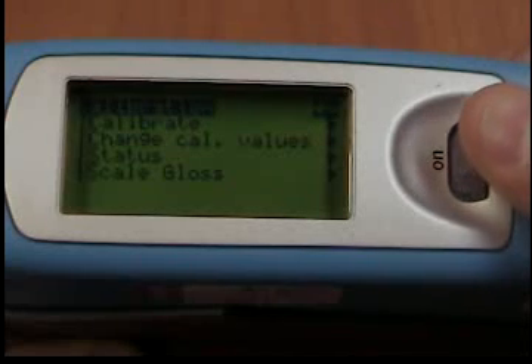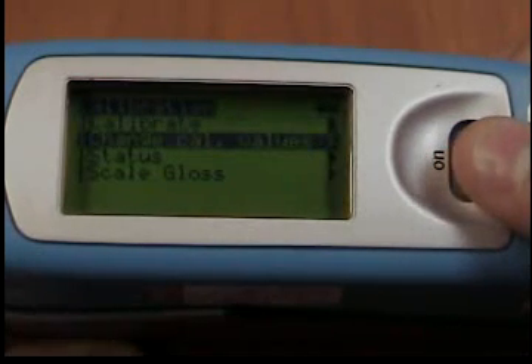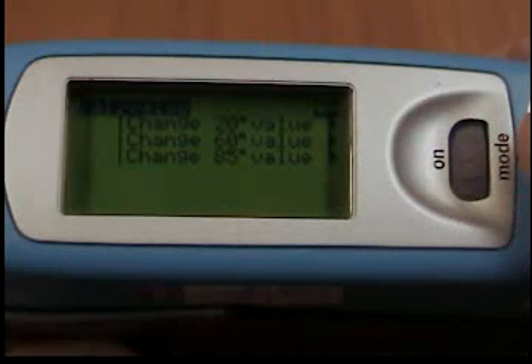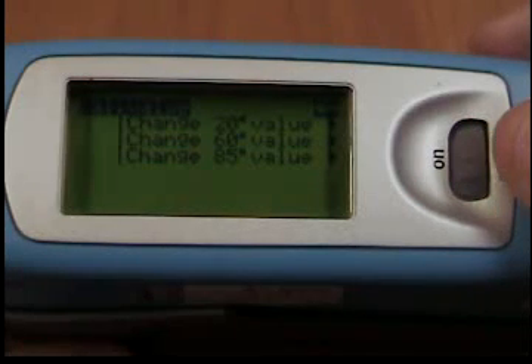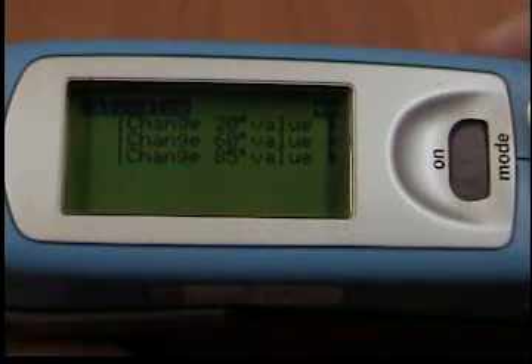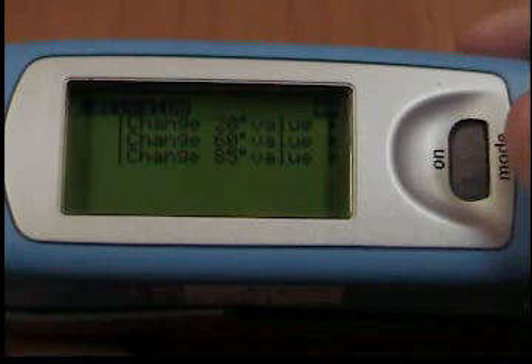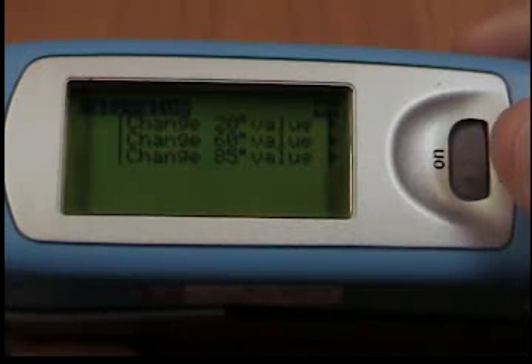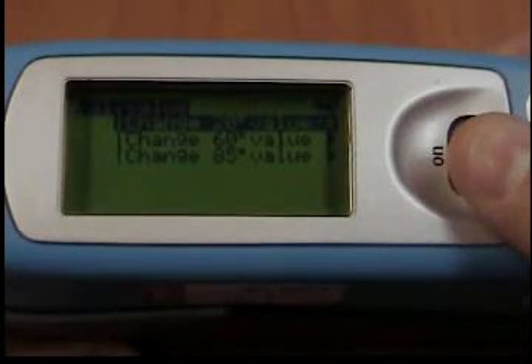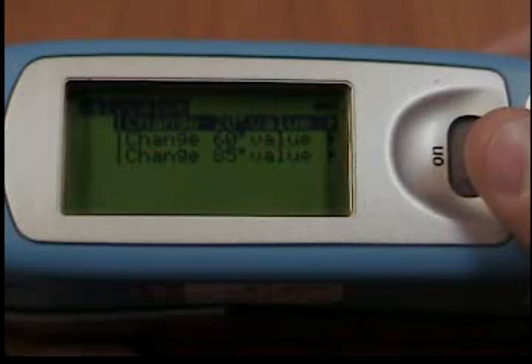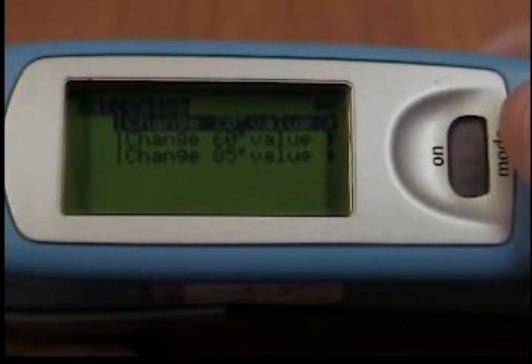Changing calibration values. The gloss values of the calibration standard in the holder included with delivery are saved in the measuring device. During automatic calibration, the data is assigned to the standard in the holder. In some cases, it will be necessary to enter data for a new calibration standard. For example, if there is a previous standard that has been damaged or scratched. To ensure exact calibration, only original standards from the manufacturer should be used.